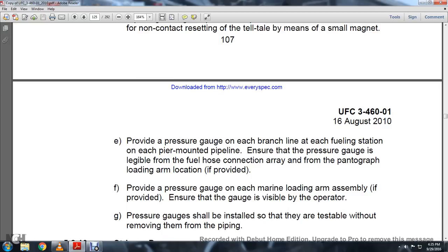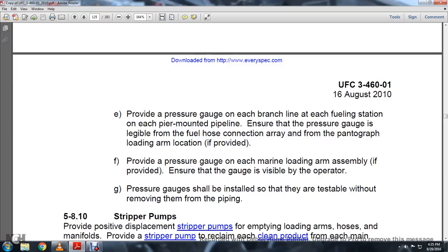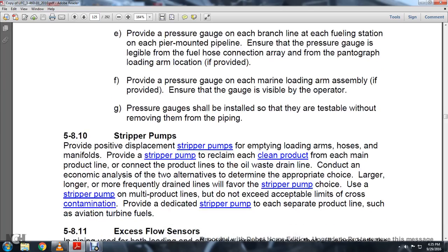Ensure the pressure gauge is legible at the fuel hose connection array with the pantographic loading arms in the location as provided. Provide a pressure gauge on each marine loading arm assembly. If provided, ensure the gauge is visible to the operator. Pressure gauges should be installed so that they are testable without removing them from the pipe.